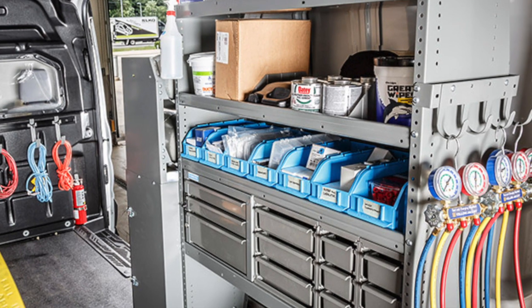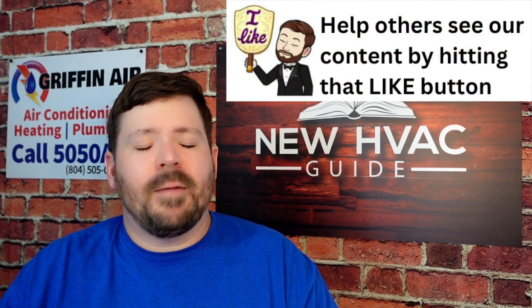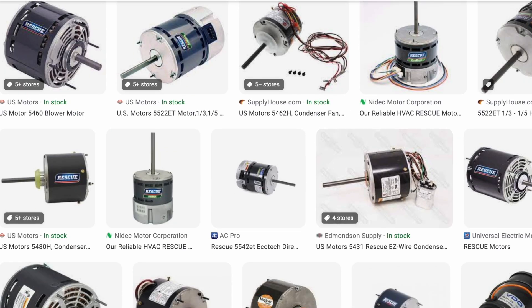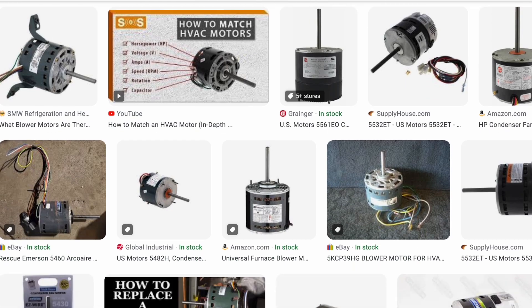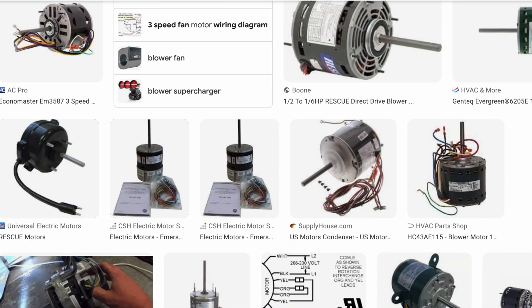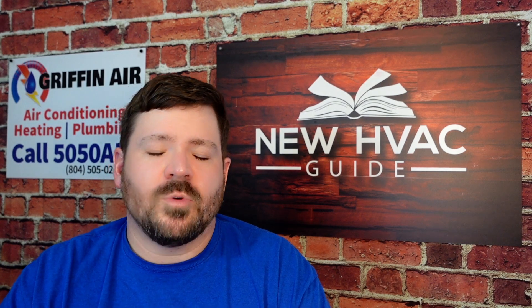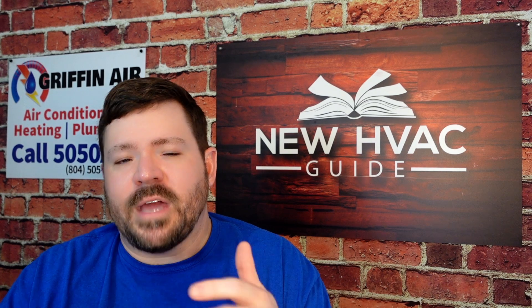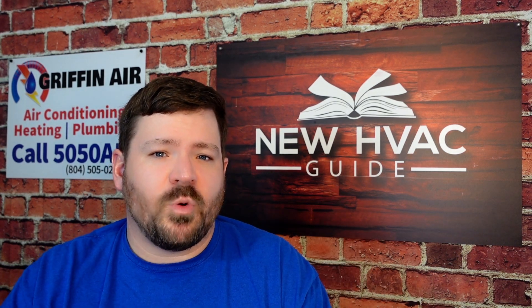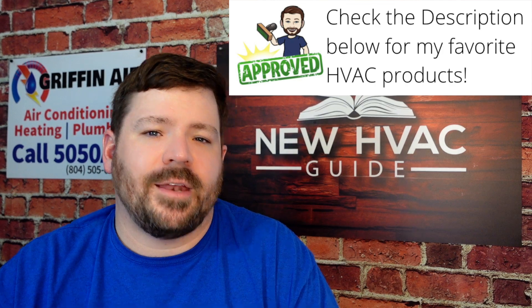I would even go so far as to say that motors are somewhat — and I'm not saying they're fully interchangeable, because there are tons of different motors: variable speed ECM, old PSC motors, single speeds, variable speeds, different RPMs and horsepower ratings. But most good heating and air technicians should have some sort of rescue motor on their truck. Even if a system has a variable speed motor, you might be able to put a rescue motor in, wire it straight to line voltage for a constant fan, as a temporary fix until you can get the actual motor in — at least giving the homeowner AC for the night.